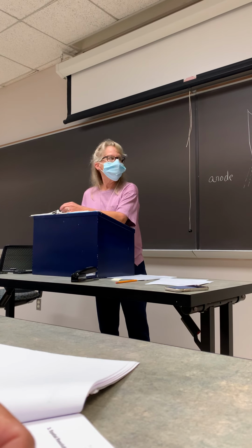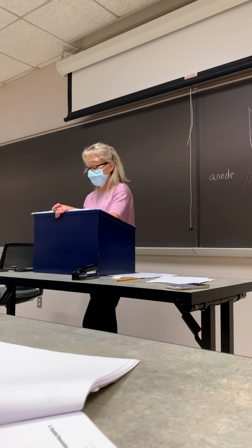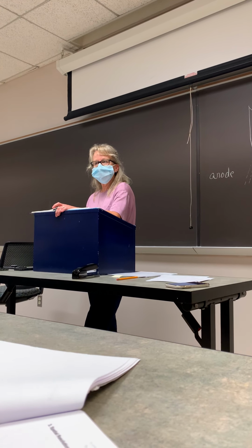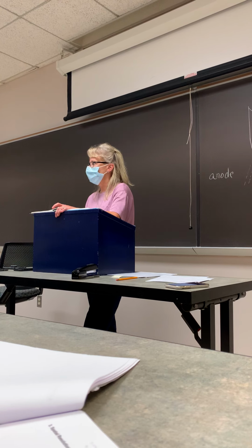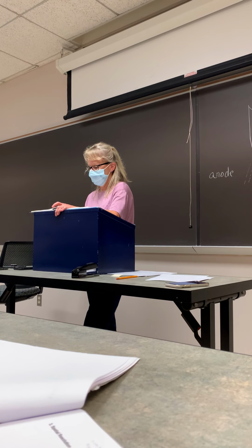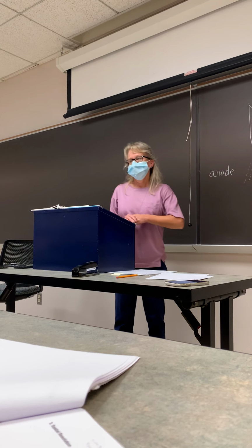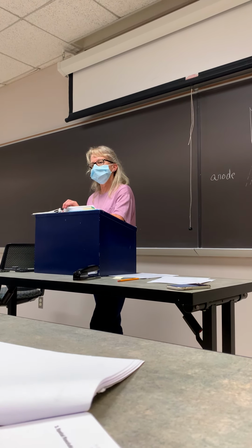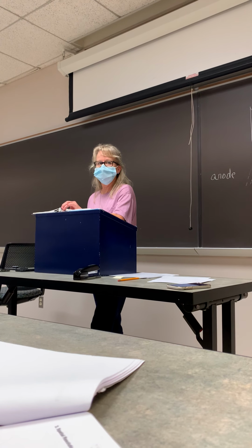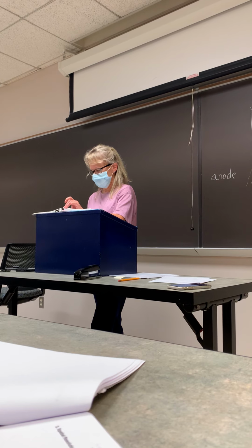Okay, focal spot size is the last one that is considered a geometric factor. Increasing the focal spot size decreases spatial resolution. You get more spreading of the image. So increasing focal spot size decreases spatial resolution. The smaller the focal spot, the better the spatial resolution.